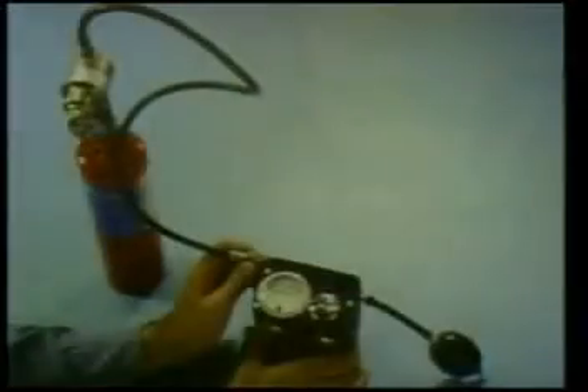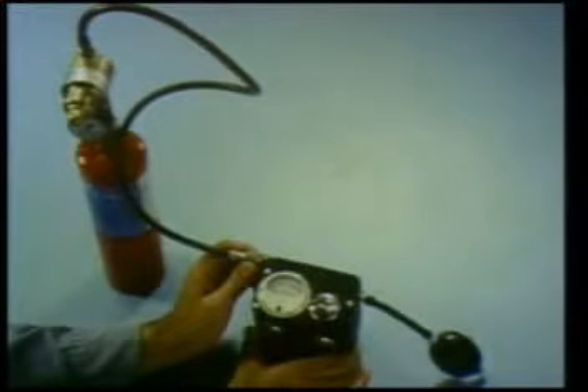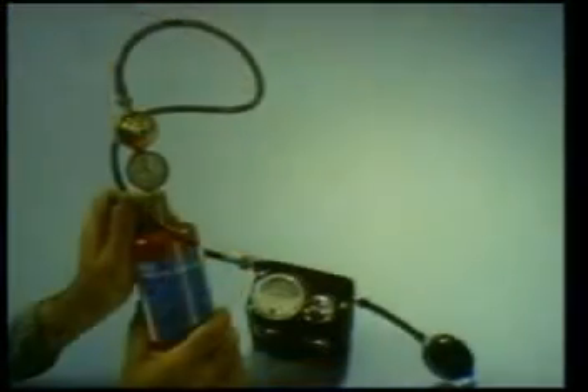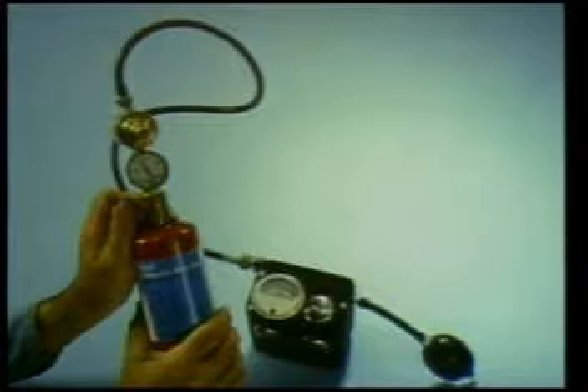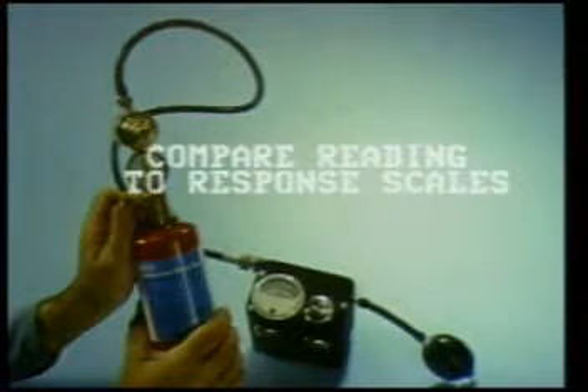To use the Model R calibration check kit, zero the instrument, then connect the adapter hose from the cylinder of calibration gas to the inlet of the instrument. When you open the flow control valve, calibration gas enters the instrument. You don't have to use the aspirator bulb. When the meter reading stabilizes, compare it to the response scales furnished with the kit. If the instrument doesn't read within the acceptable range, replace the detector filament.